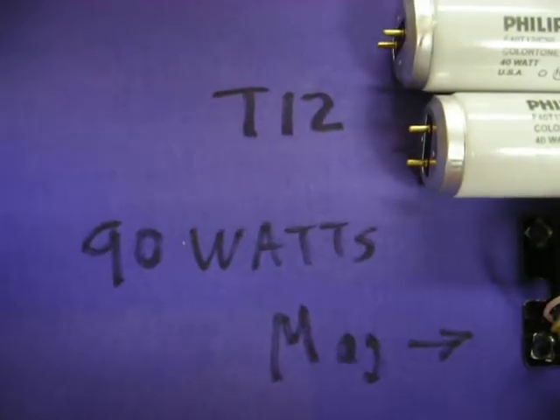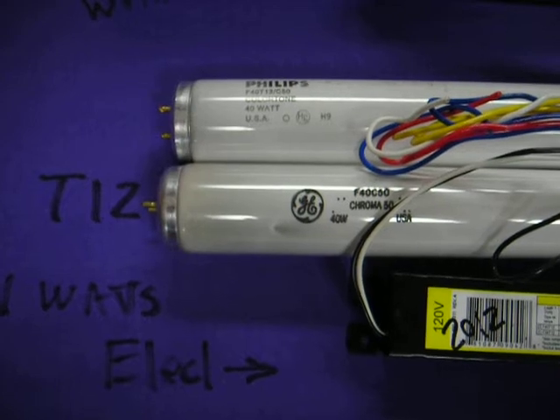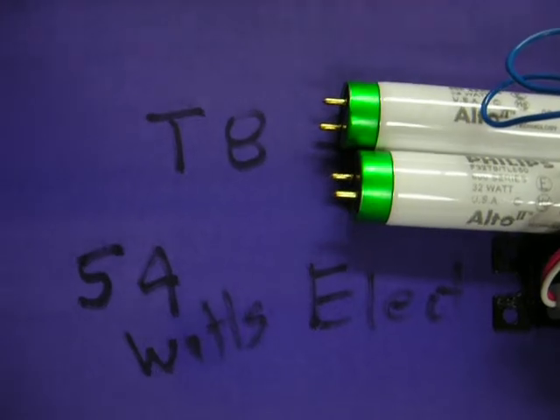So I've measured this across three or four different fixtures. It's 90 watts with the T12 with the old magnetic ballast, 71 watts with T12s with a modern electronic ballast, and all the way down to 54 watts when you go to the T8 with an electronic ballast.